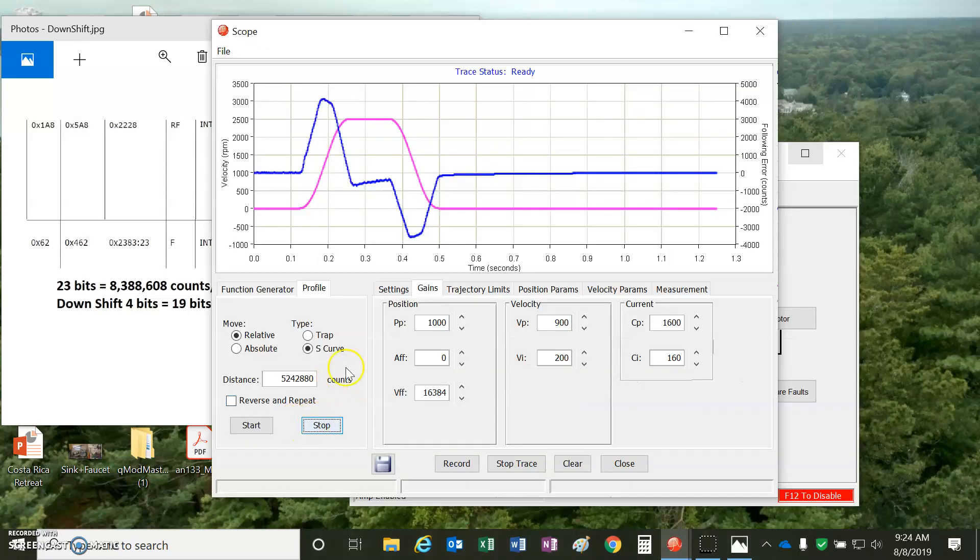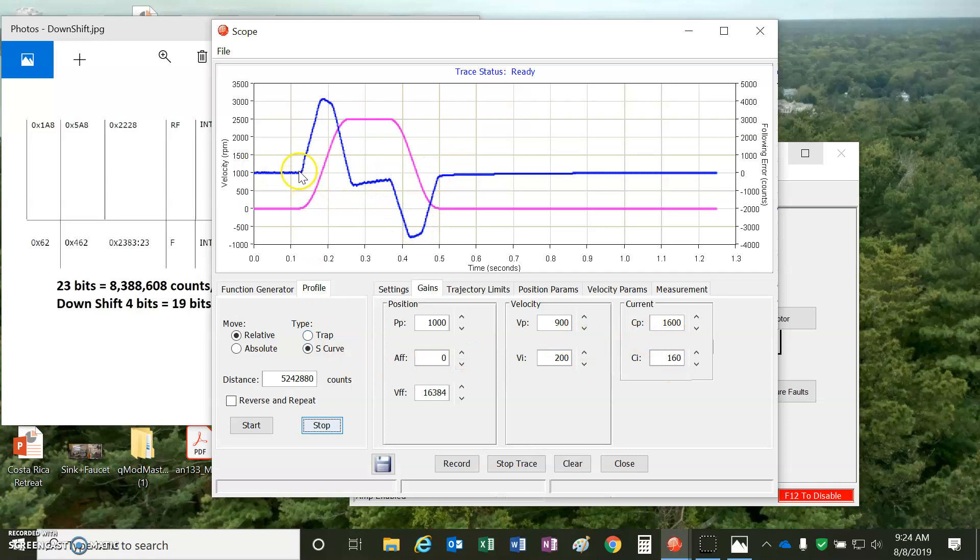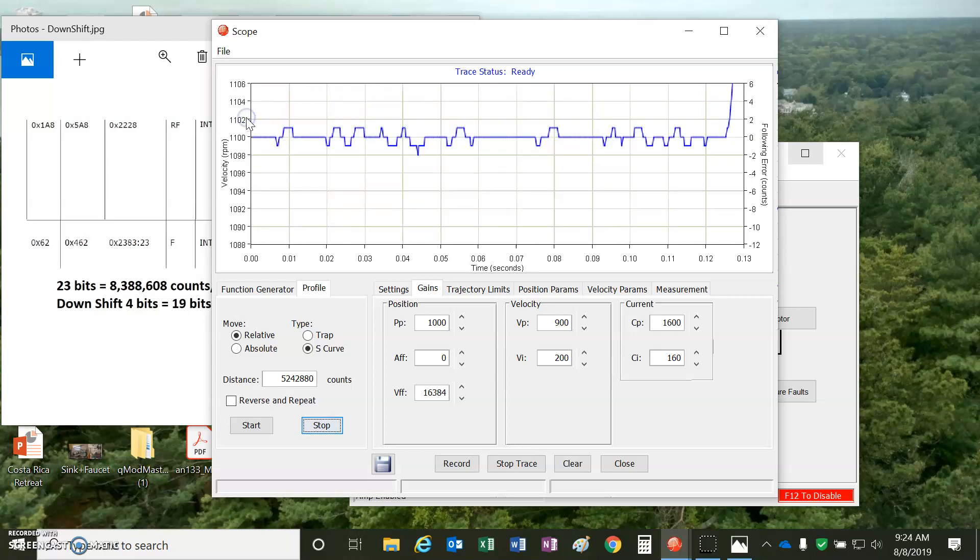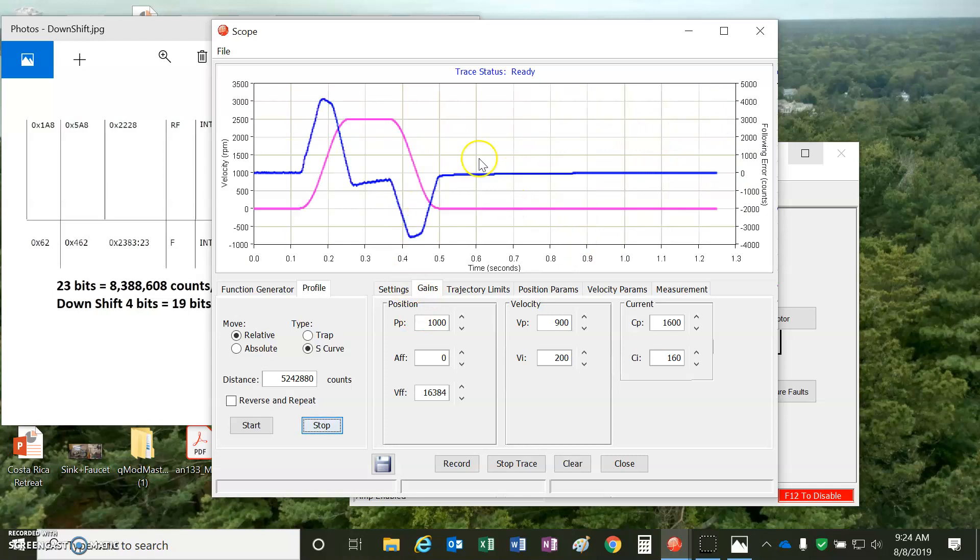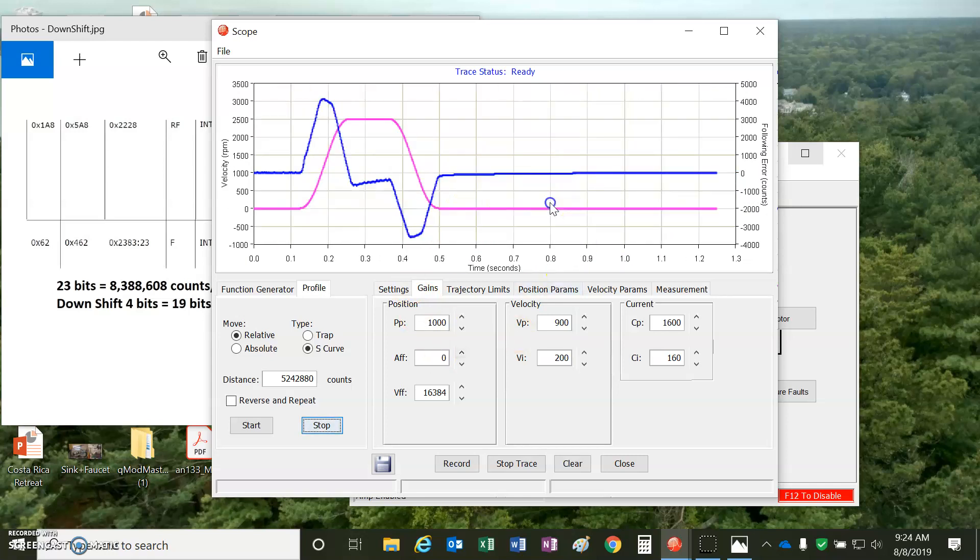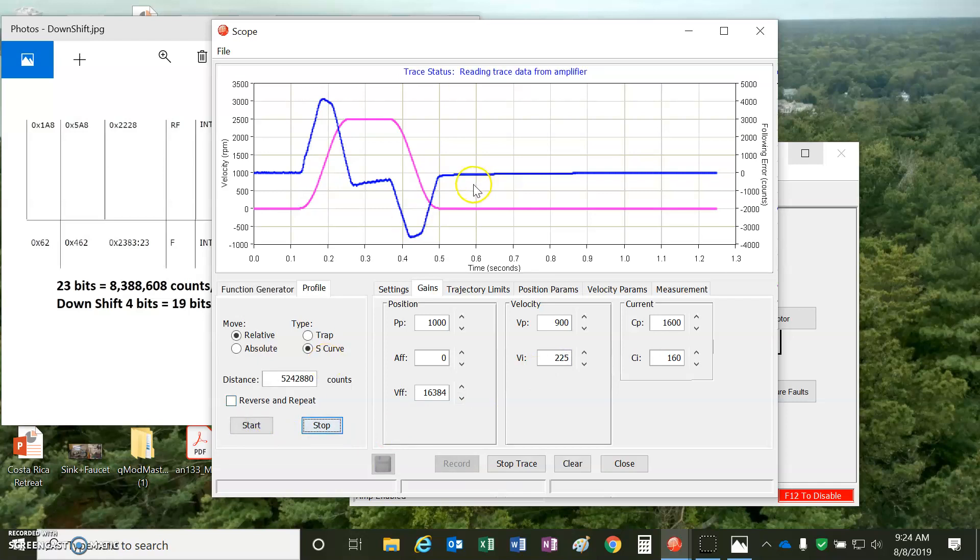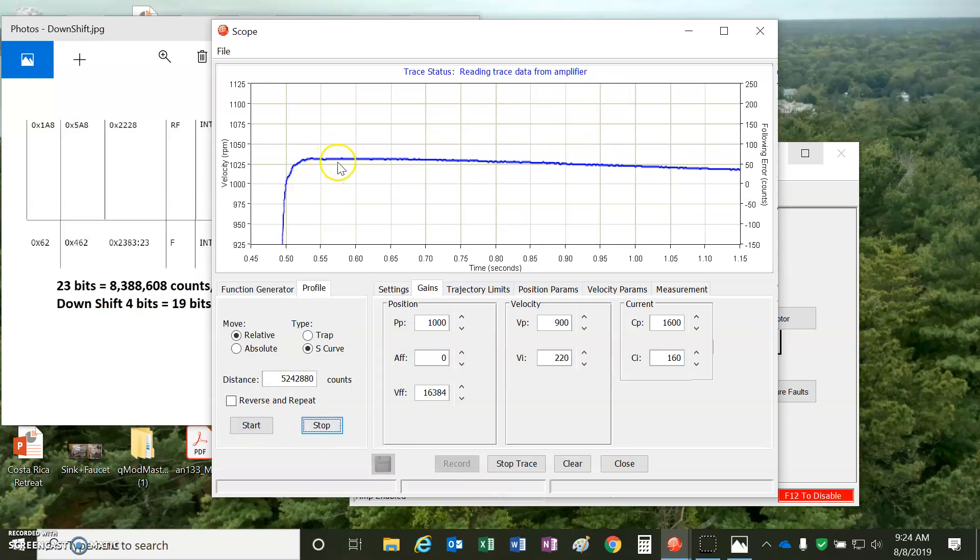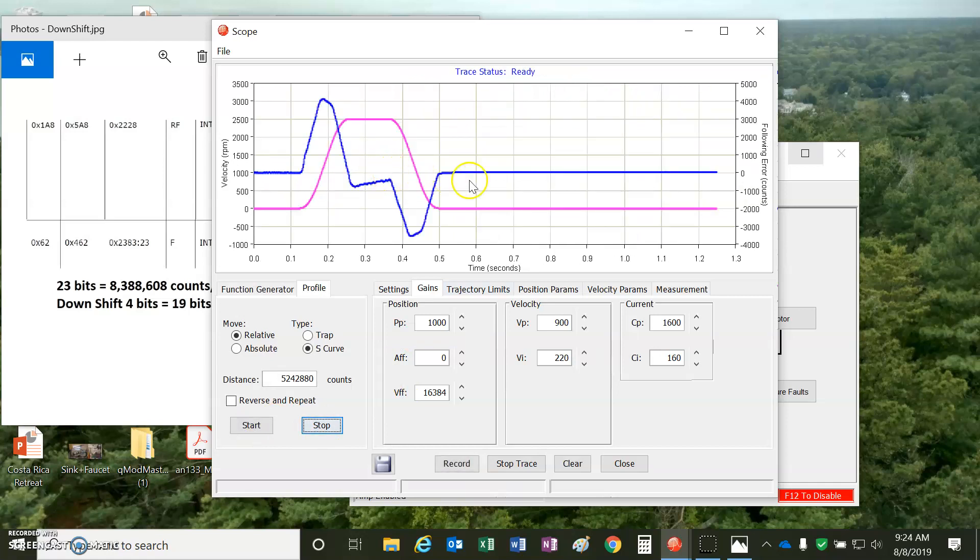But so taking a look at the move again with a higher current loop bandwidth, I did notice that the steady state got a little better, plus or minus a count. So maybe it does help. We could increase the integral a little bit. We try to get to steady state a little quicker. We're still within 100 count window, but you can see when the integral is high, it overcompensates a bit.